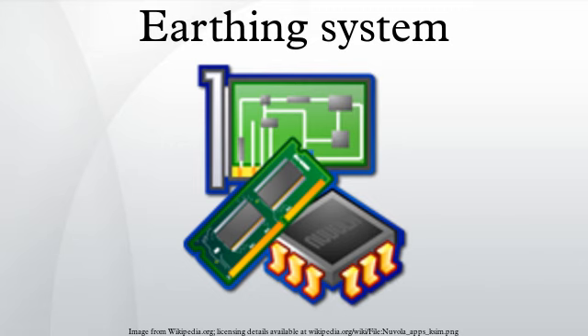However, while the fault is present, the potential of other two phases relative to the ground reaches √3 of the normal operating voltage, creating additional stress for the insulation. Insulation failures may inflict additional ground faults in the system, now with much higher currents. Presence of uninterrupted ground fault may pose a significant safety risk. If the current exceeds 4–5 A an electric arc develops, which may be sustained even after the fault is cleared. For that reason, they are chiefly limited to underground and submarine networks, and industrial applications, where the reliability need is high and probability of human contact relatively low.